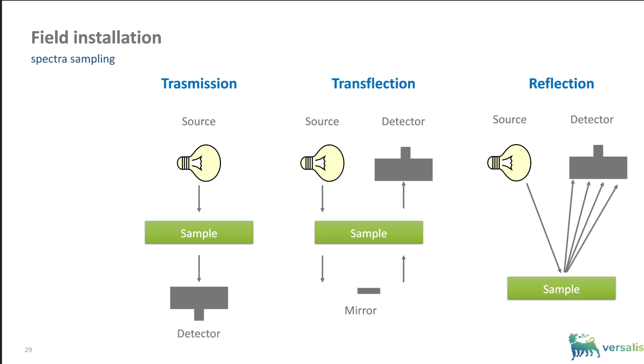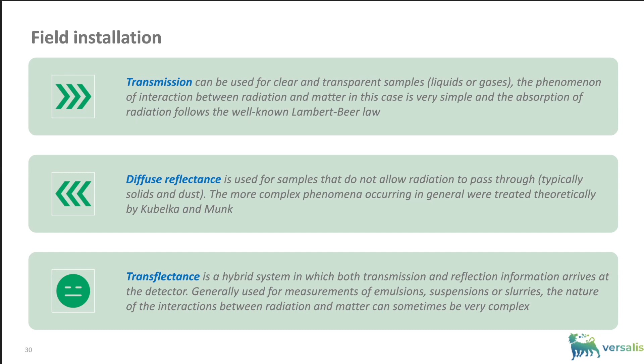we can have mainly three kinds of probes, three typologies of probes, at least from the leading manufacturers such as Hellma. They can work in transmission, reflection, or in an intermediate configuration, transflectance. Transmission is the simplest configuration and can usually be used for clean fluids such as liquids. Reflectance is generally used for more critical cases, typically fluids that do not allow good radiation passage. Transflectance is a more special case. It is a hybrid between the two previous solutions and can therefore be used for specific fluids.